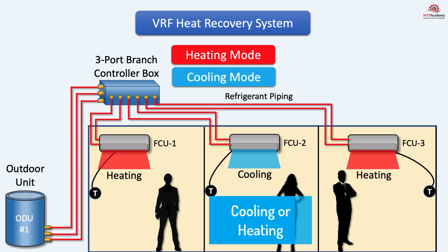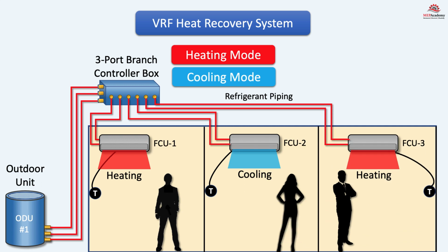The same for fan coil number 3. We just pipe the fan coil to the branch controller box, and that office can choose any mode of operation, in this case heating. This can all be done using one outdoor unit with a 3-port branch controller, which is one of the advantages of using a heat recovery system as opposed to a VRF heat pump system.